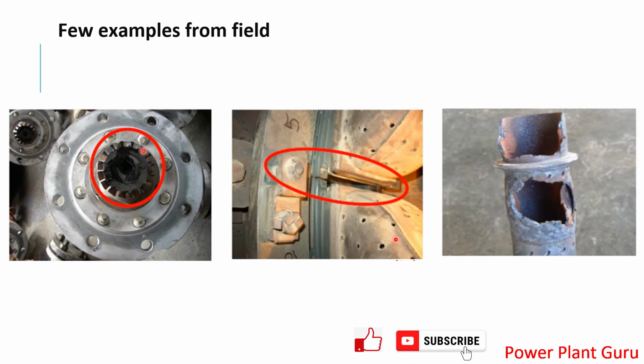Every combustion can should ideally carry the same amount of liquid or gas fuel, or a mix, with the same amount of air. But what if I am reducing the air to one of them? Accordingly, the fuel mix would change and the temperature going into that particular zone will definitely change. So that will cause another type of spread issue in these machines.